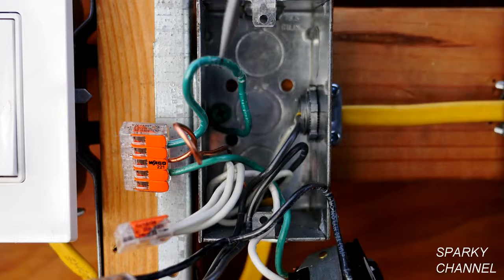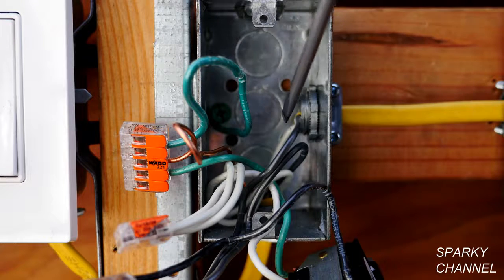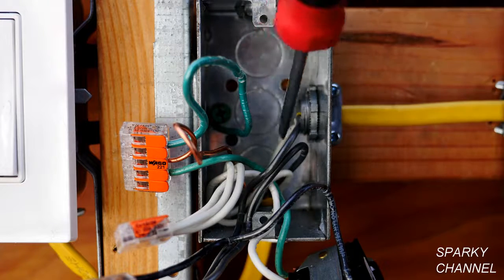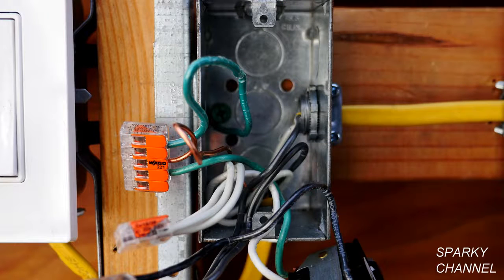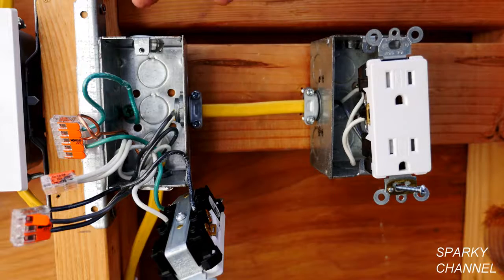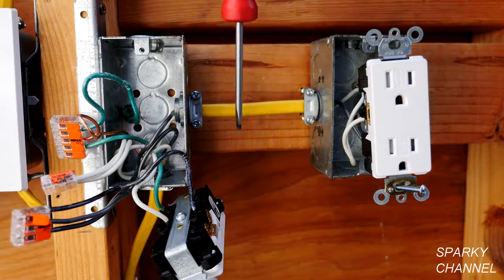This box has been upgraded to have grounding, but the next box has not been upgraded yet. So that's how we got to this situation where this box was grounded, but the adjacent box is not grounded. So we've identified the problem. Now we have to determine if we can solve this problem by changing out this cable.